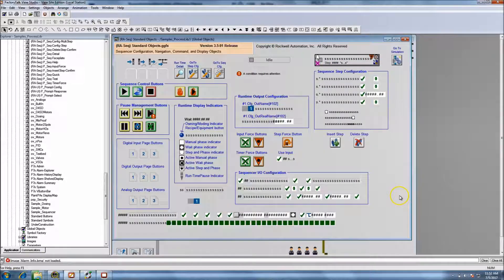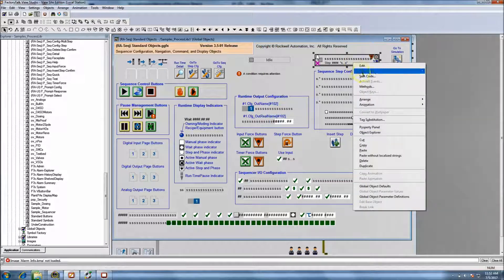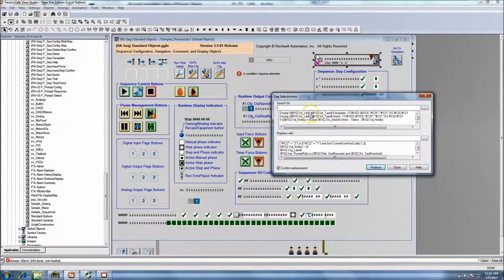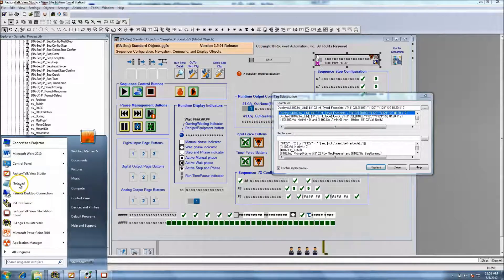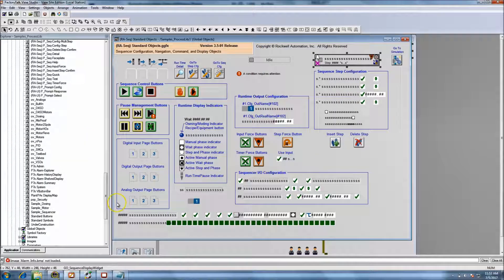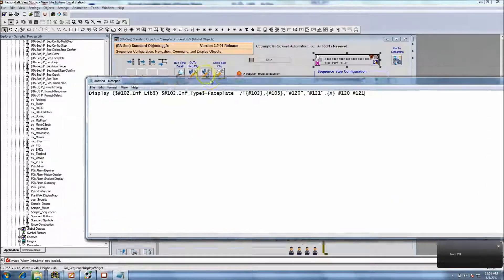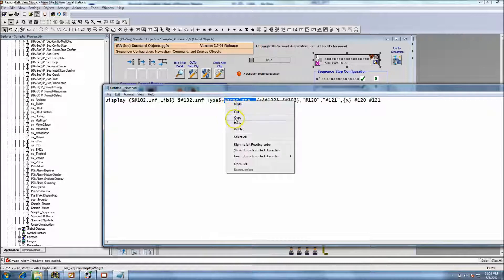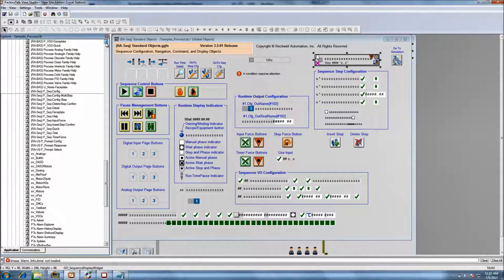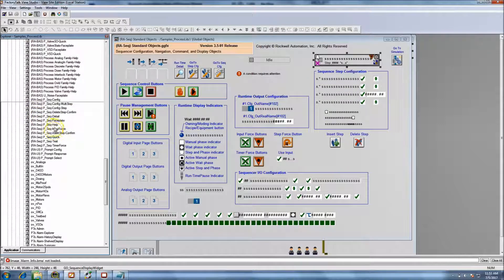What we have to do is edit the base object - you're not really editing it, you're just trying to find it. At that point you can hit tag substitution and look for the screen that's being called up. We're looking for a display - you have the face plate or the quick view. Over on the side we can copy this into notepad, which is probably my favorite tool. What's important is understanding what display I'm pulling up - I'm looking for RA sequence and then faceplate right here.